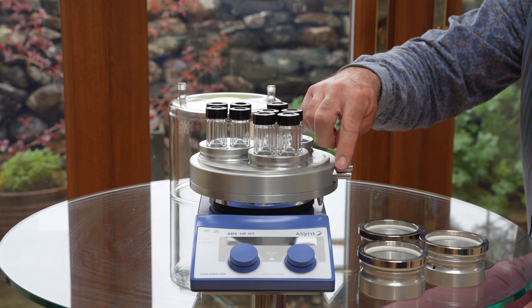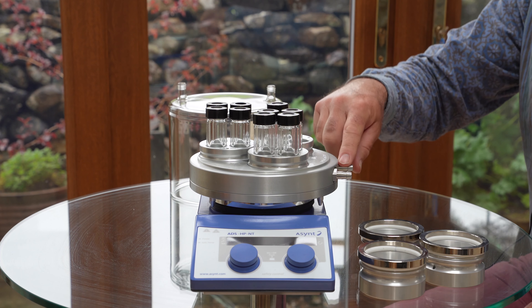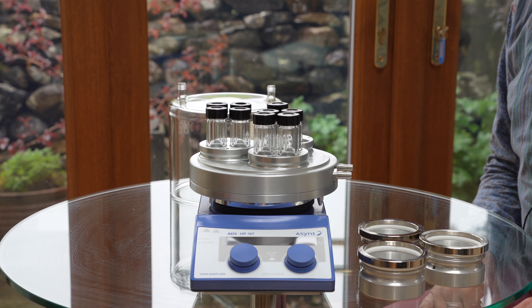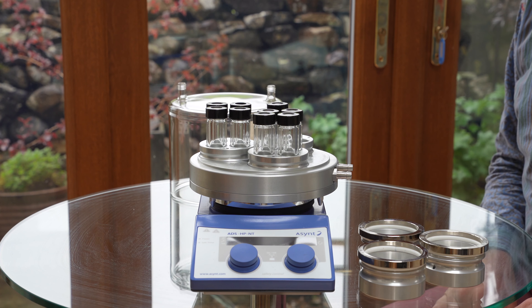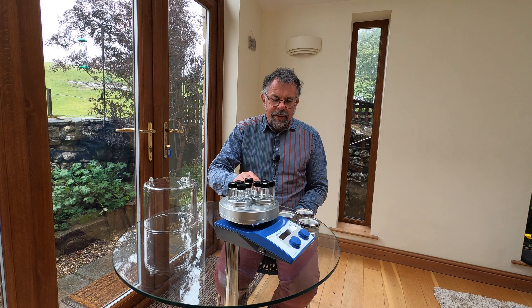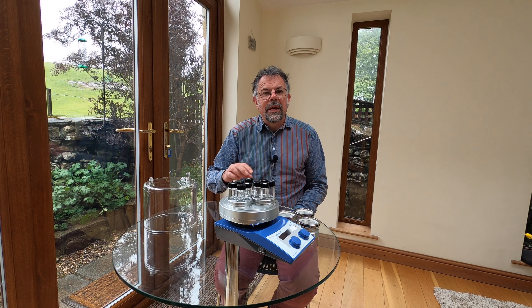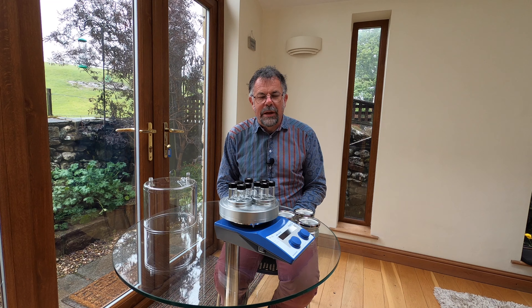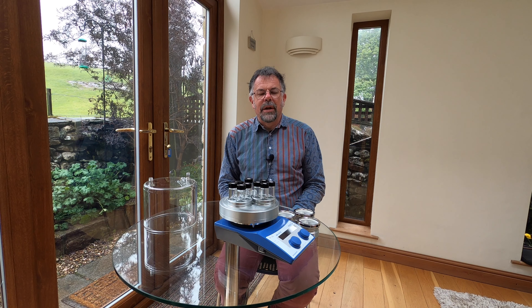The Snowstorm units use a heating and cooling circuit from a standard regular circulator such as Julabo, Huber, or Grant. It comes with a standard hose barb fitting, but that can be easily swapped for an M16 for a higher performance connection, especially when running at lower temperatures.